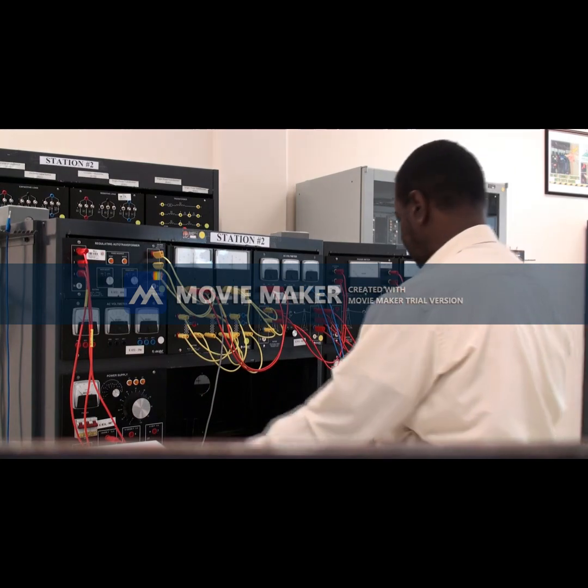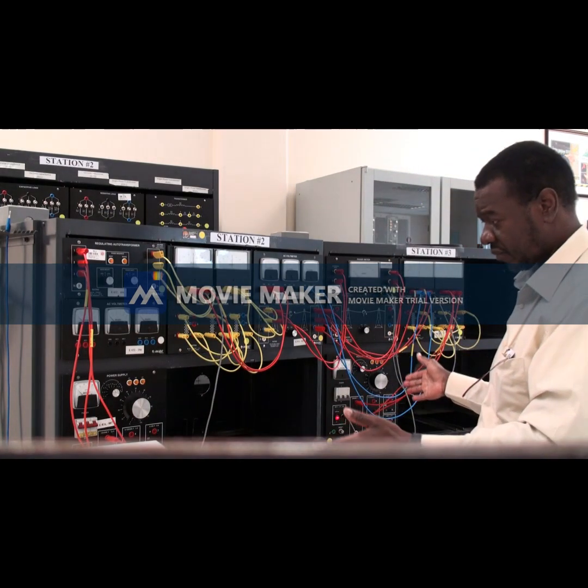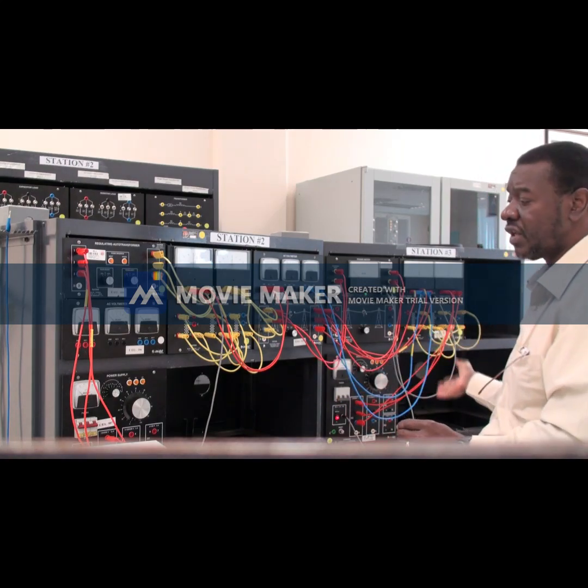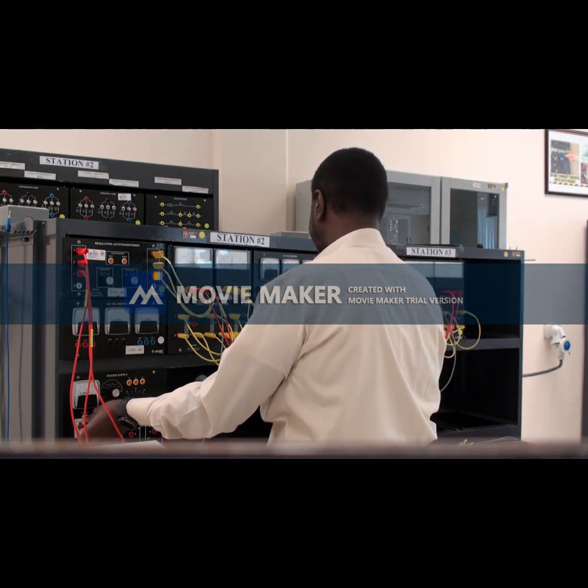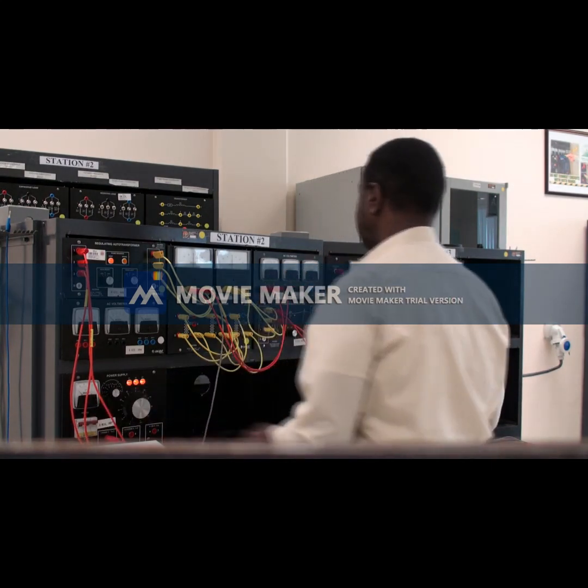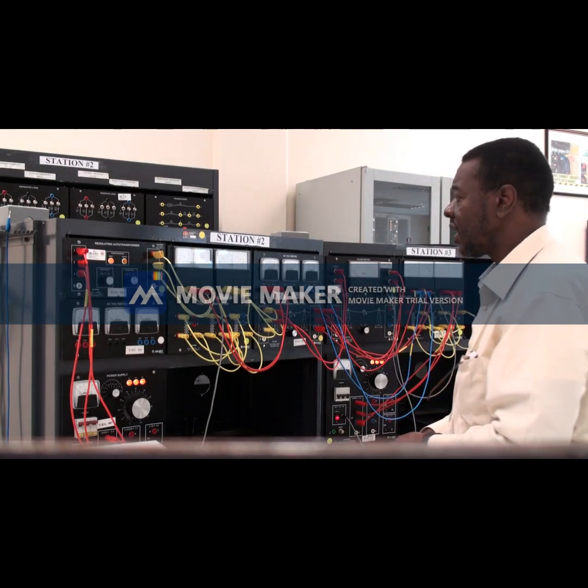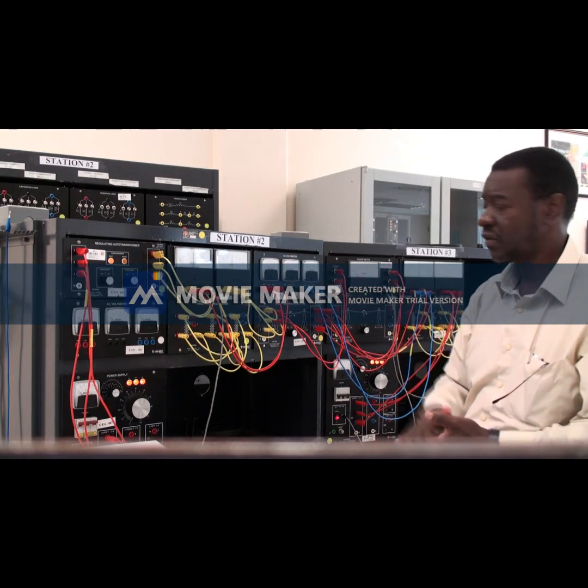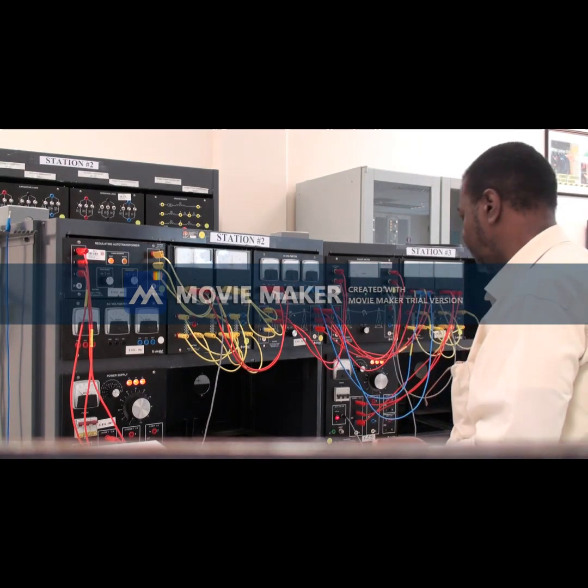Our angle is equal to zero, so both of them are in phase. By the way, to make sure that we have the same voltage, we use the fixed terminals 1, 2, 3, 1, 2, 3 in both stations. So we switch on both stations here, and then we have both of them on 220 volt. The angle between them is 0, so we can see that there is no power flow, either from either station.